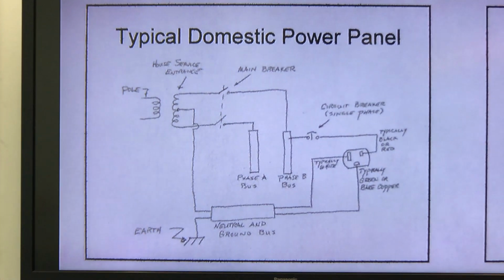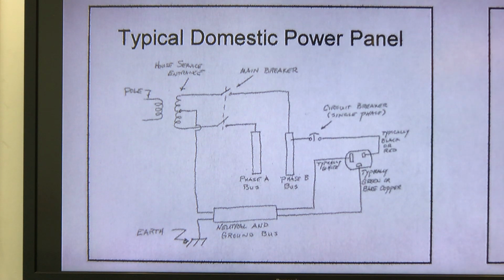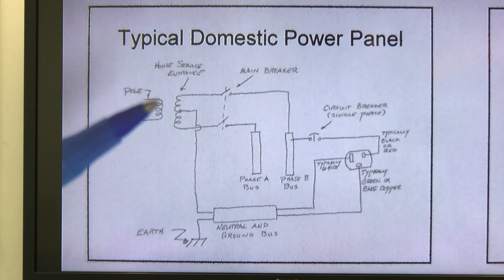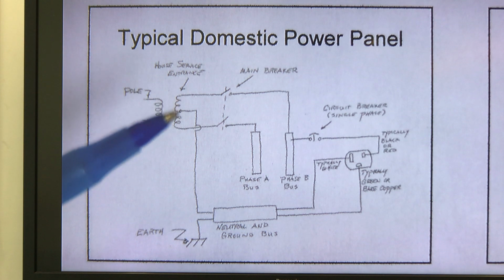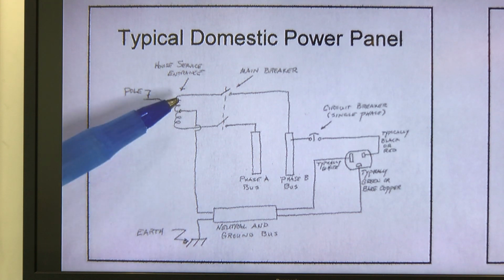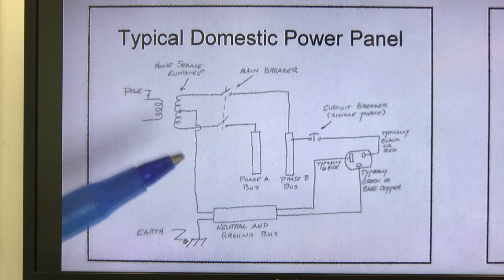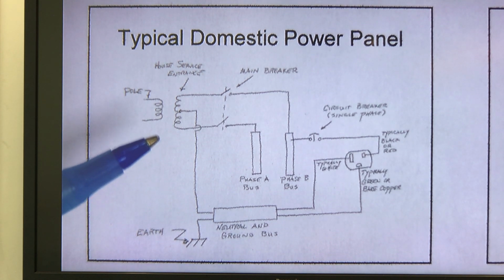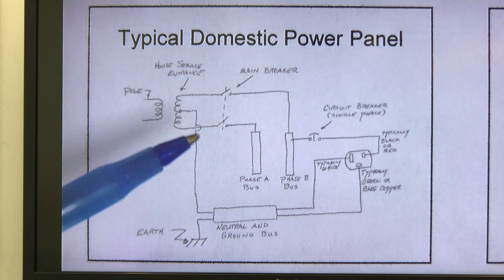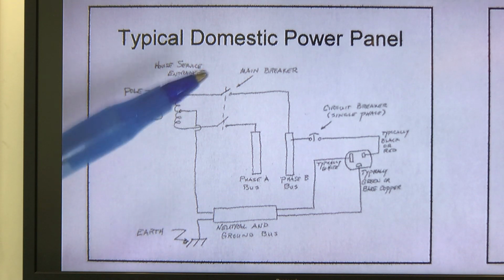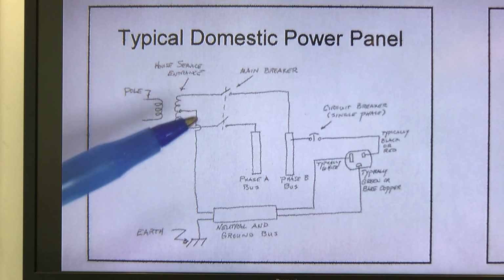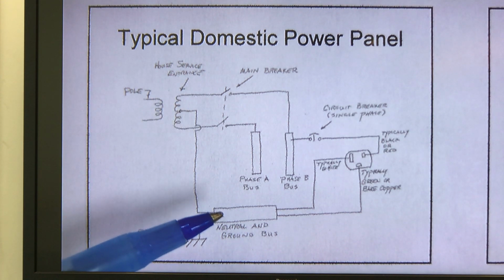In the typical domestic power panel, what you think of as the connection from the pole is actually the primary side of the transformer. So this is the thing that's in the air, and you don't really see it by your house as a rule. What you do see at the house is the secondary side of a transformer that's center tapped. And this is usually what's called the service entrance. More often than not, this contraption is mounted on a pole or maybe on a pad close to where you live. And the connections that you see are the ones that actually go into the house. So you'll have two phase lines, they're called, and then a center tap. The center tap is actually your neutral.